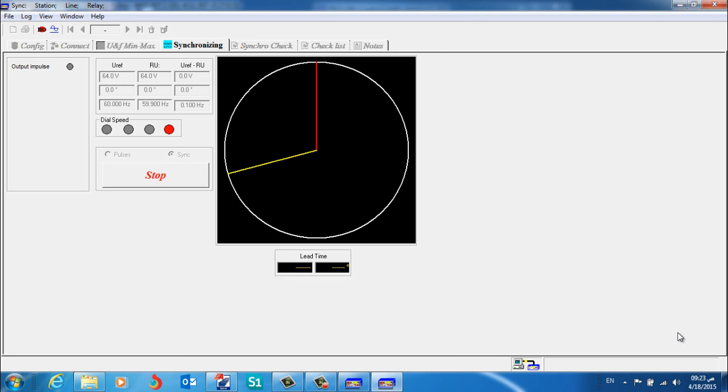So now we tested if VT MCB trip will prevent our sync. Now we remove this MCB trip. We will check here output. Okay, it's coming sync. See, closed, okay, and stop the freq.